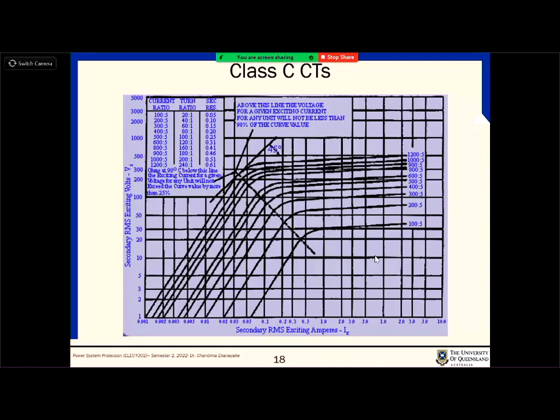These are the typical class C characteristics. You will see them in a lot of different standards. What it means is, you can see that the horizontal axis is IE, which is the excitation current. The vertical axis is the secondary voltage. And then you have different current ratios, from 100 to 5 to 1200 to 5. Right? For different current ratios, you will have different curves.